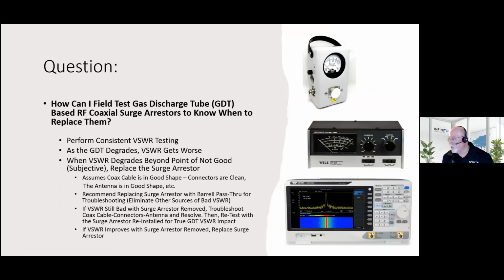But I understand now they're much more sophisticated and sometimes built into the radio itself or some gadget in a 19-inch rack. But that's basically all you're doing. As the gas tube degrades, it negatively impacts VSWR, which gets worse. And what I tell folks is, let's say you think that the surge arrestor is bad. Before you jump to that conclusion, replace the surge arrestor with a barrel pass-through and then retest. And if the VSWR gets better, bingo, it's the surge arrestor, replace it. If your VSWR stays bad, well, something else is wrong.